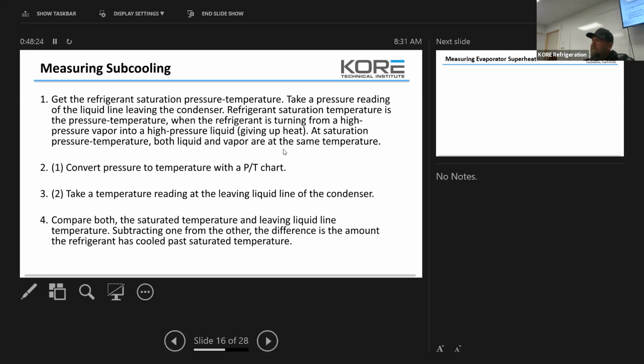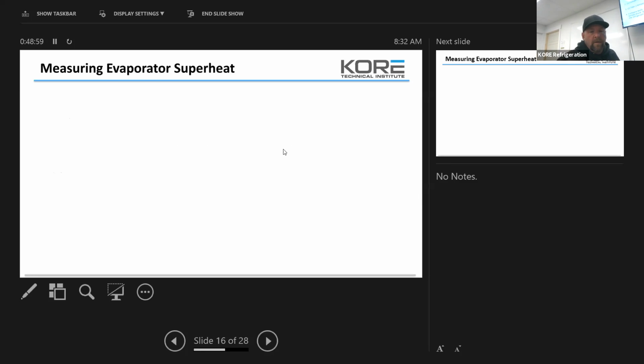Because what that's telling me is how much heat pickup potential I have at the evaporator, and that's how ACs are working. So if they have 10 to 12 subcooling, they're going to get solid liquid to the TXV, and if they get solid liquid to the TXV, they should get X amount of heat pickup through the evaporator and then transferred back out to the condenser. Make sense? So it's a mathematical, very specific measurement way of checking to make sure that we have the right amount of heat pickup potential.